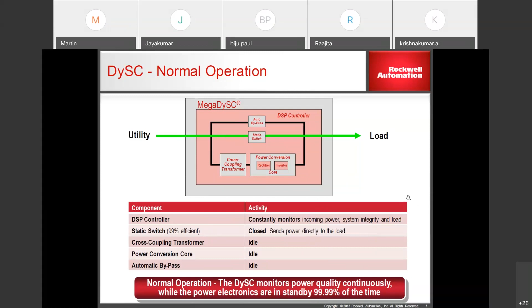We call it a voltage sag event. So let us take a live example, a 100-volt system, and the voltage falls below 87.7 volt. Then this will be the power flow path. The utility power, the green line again, represents how the power flows in this case. It is fed through the cross coupling transformer, which basically works as a voltage multiplier over here. And then we have a power conversion core, which comprises a rectifier as well as an inverter. And then this connects back to the load.